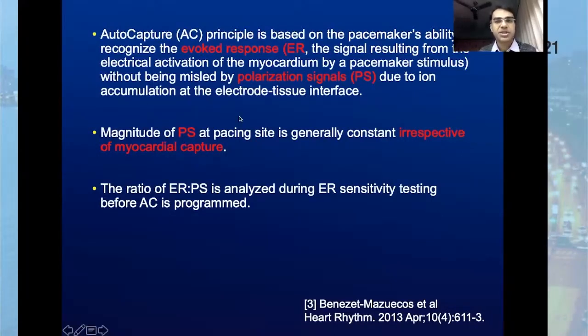The auto capture principle is based on the pacemaker's ability to recognize the evoked response. What is the evoked response? The evoked response is the signal resulting from the electrical activation of the myocardium by the pacemaker stimulus. And the auto capture has to function with this detection of the evoked response without being misled by the polarization signal or the polarization artifact. The polarization artifact is due to ion accumulation at the electrode tissue interface. The magnitude of the polarization signal at the pacing site is generally constant, irrespective of the myocardial capture. This is in contrast to the evoked response, which depends on the true myocardial capture.